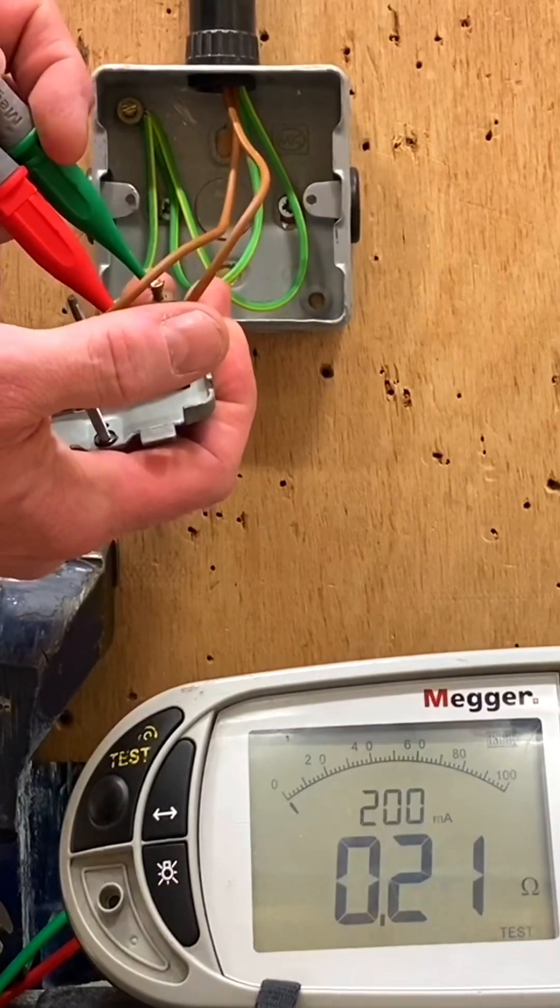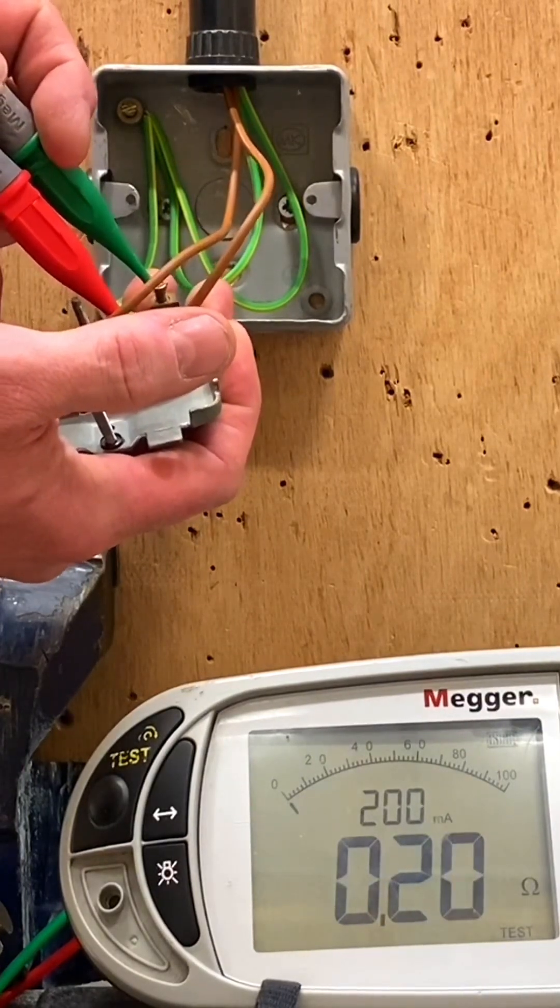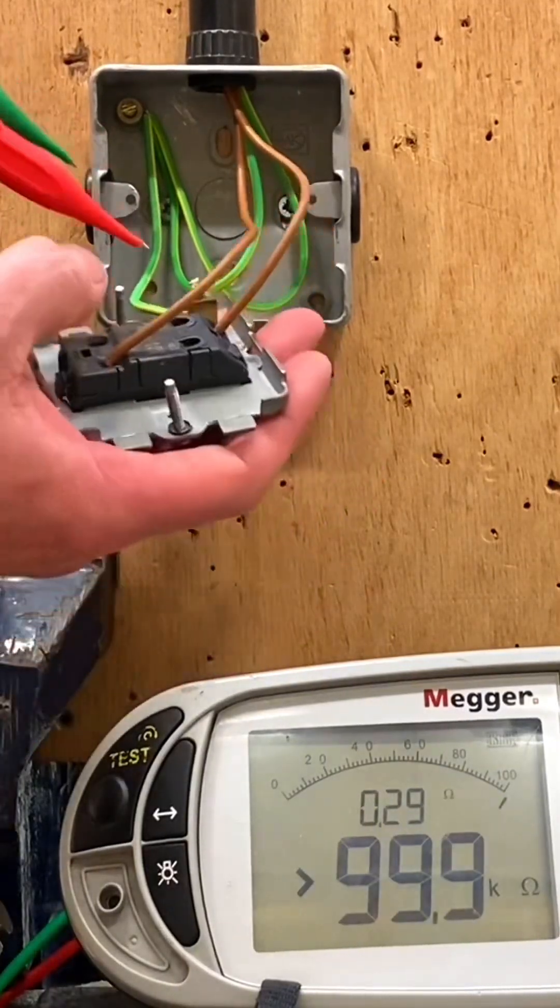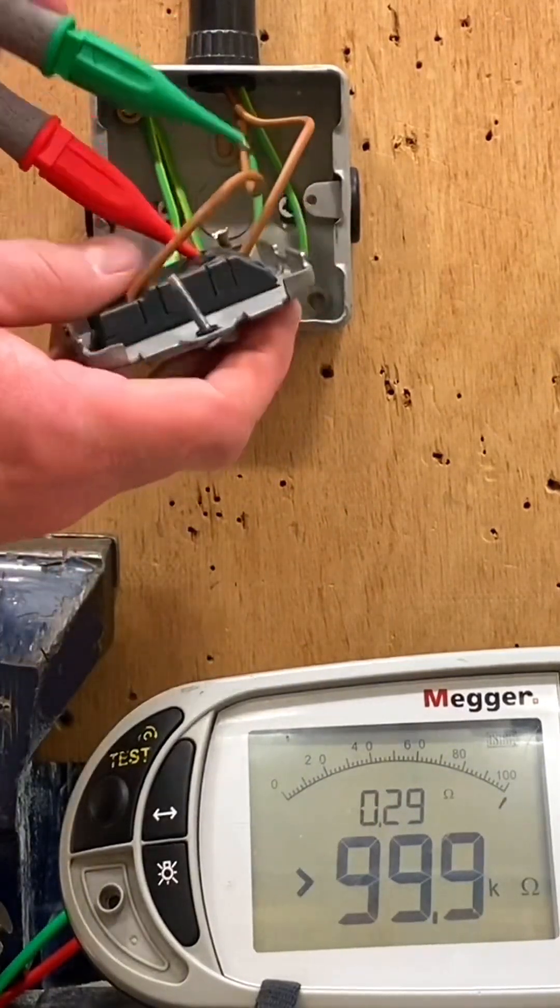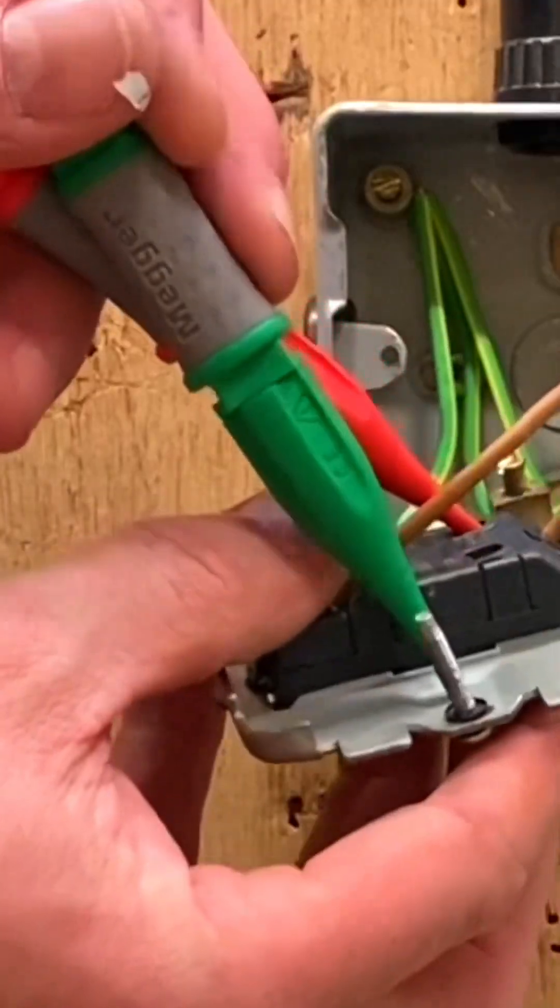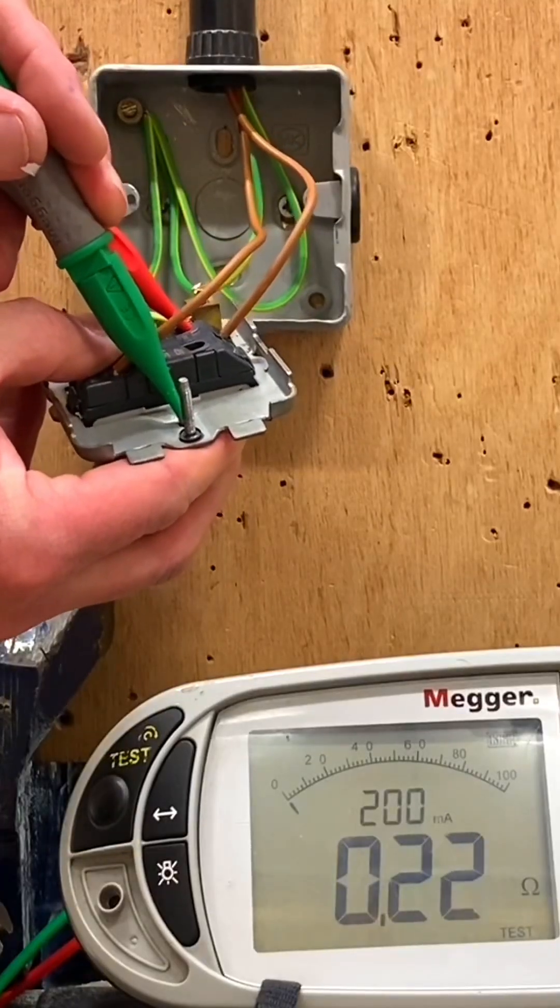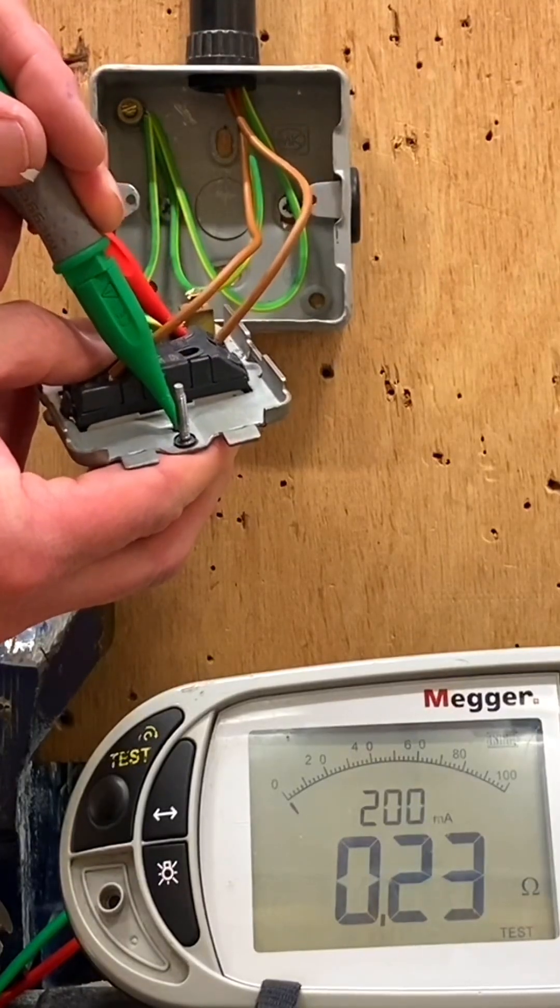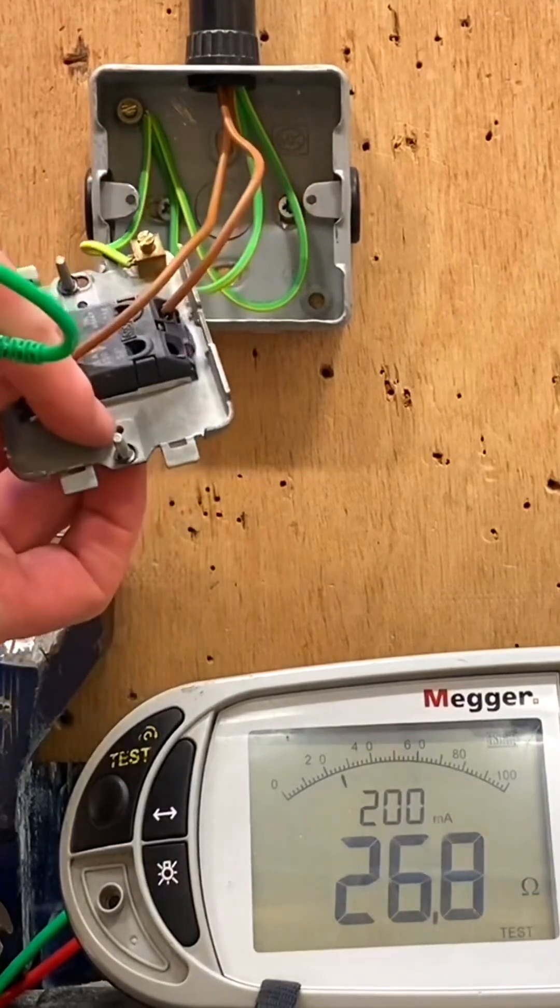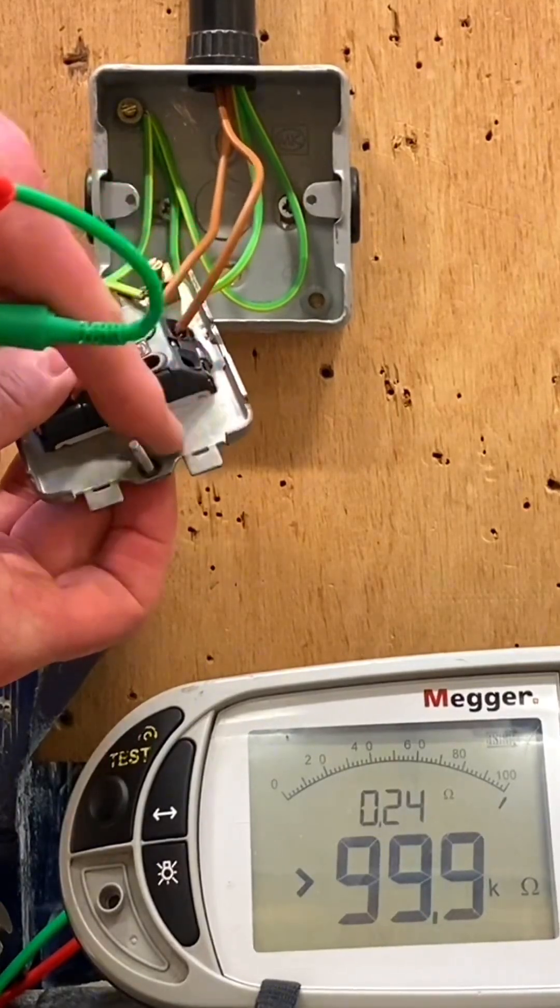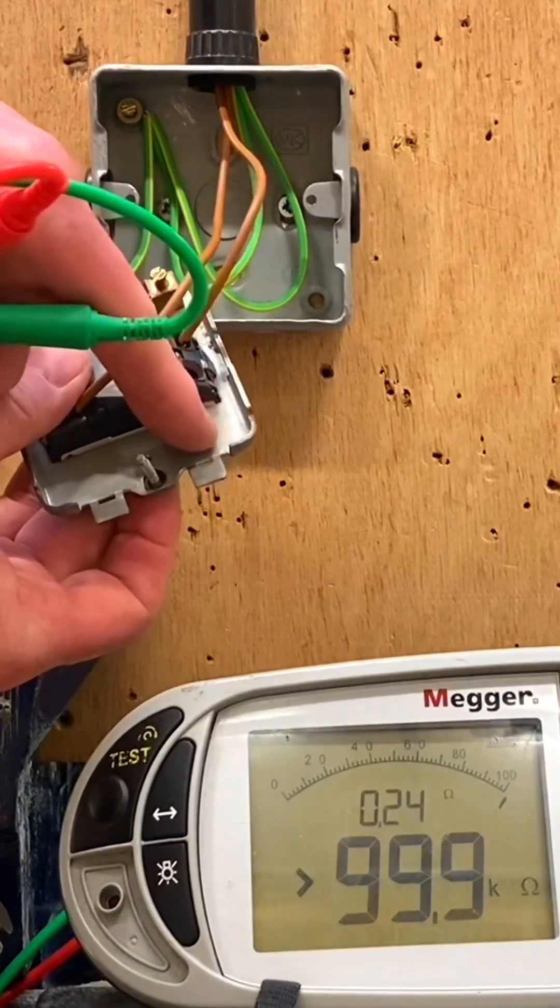Now I'm going back into common and using the hole where the threads were for one of the screws. When it settles down, I get 0.23 ohms. That's using the hole here because it's got a nice clean inside where the threads are, so you have a really good connection. If you're going to the back of the plate, you have to scratch some away to get down to the bright steel.